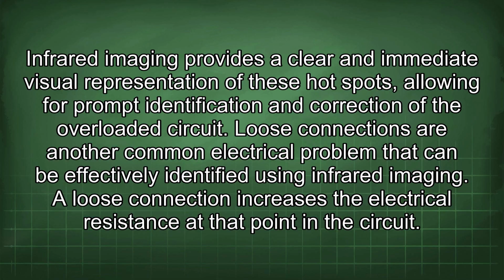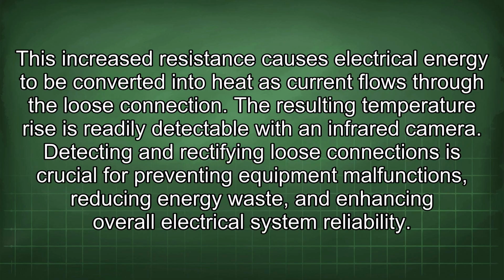A loose connection increases the electrical resistance at that point in the circuit. This increased resistance causes electrical energy to be converted into heat as current flows through the loose connection. The resulting temperature rise is readily detectable with an infrared camera. Detecting and rectifying loose connections is crucial for preventing equipment malfunctions, reducing energy waste, and enhancing overall electrical system reliability.